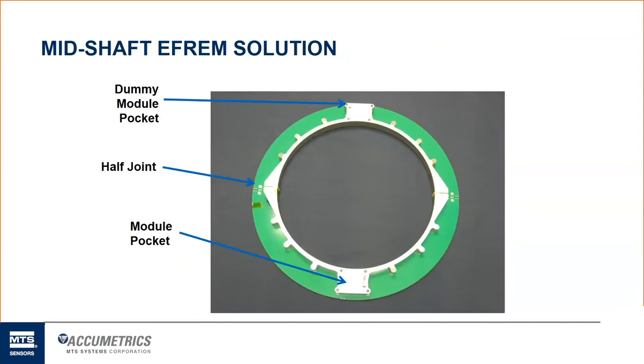So here's an example of the mid-shaft EFREM transmitter. It's a two-piece split collar design that has an electronic module on one half, and then a weighted dummy module on the other half that weighs the exact same as the electronic module. It's connected across this half joint here with high-strength Unbrako bolts, which is how we make that contact, and it's torqued down to each shaft. There's a specific torque rating in every manual dependent on the size of the shaft as well as the speed of the machine itself.